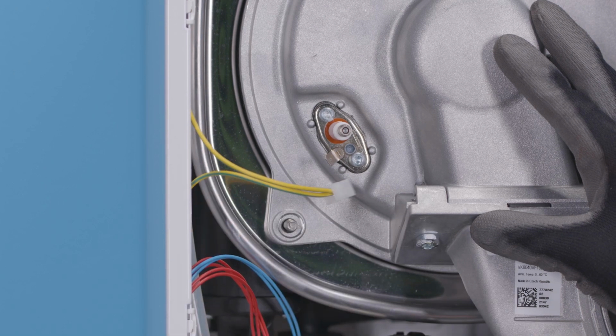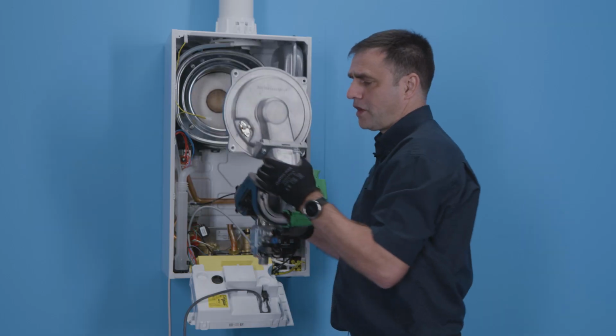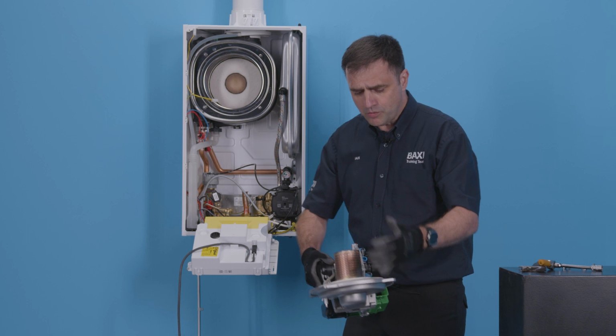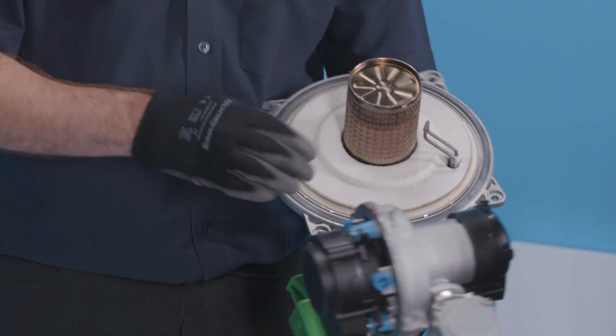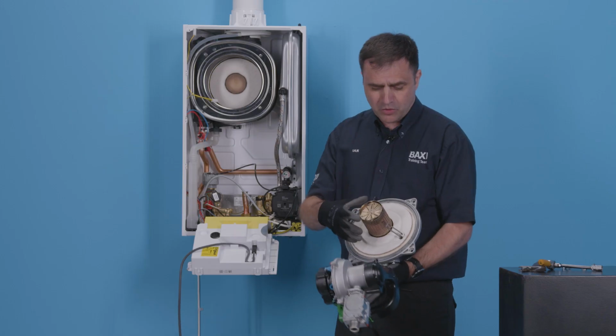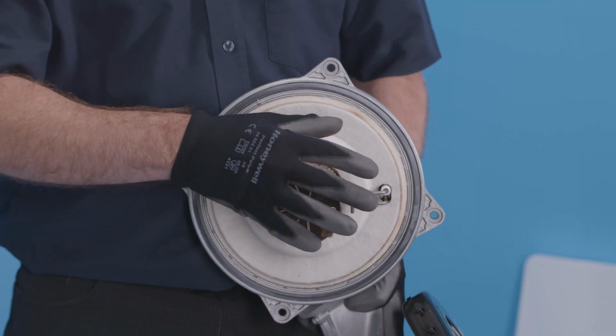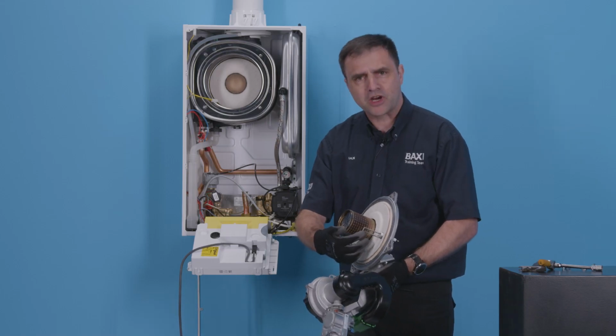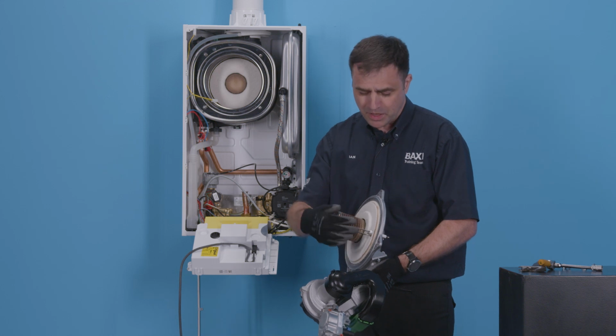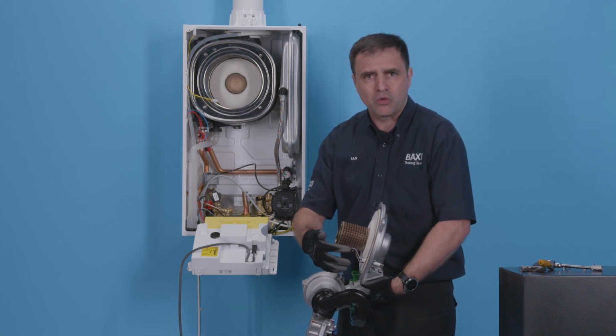Remove the spark electrode and its earth tag, and then the whole section comes away. Now, what I'm looking for if I'm going to do this in a service, I'm looking for the insulation round here. I'm looking at the state of the burner, making sure there's no debris build up. Make sure your electrodes are about 3-4mm apart, and make sure that the edge is parallel with the burner.